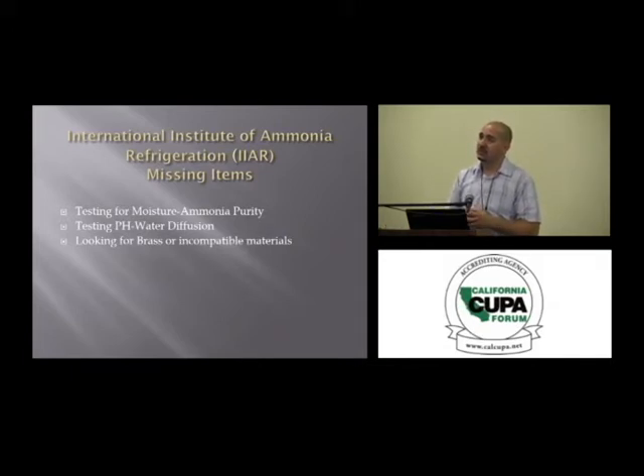Sometimes we've seen where they use brass caps to cap a valve. There was one instance where, according to the facility, they had installed a new compressor, and the compressor came with a little brass gate or isolation valve, and within time it started leaking ammonia, and then they found out that's what the problem was. And when you see the turquoise corrosion on any kind of brass material, you know that you've got ammonia being introduced to that metal. And again, it's very corrosive and it will leak.